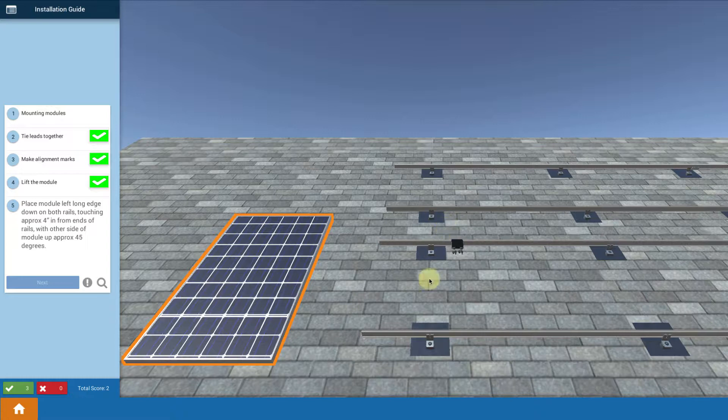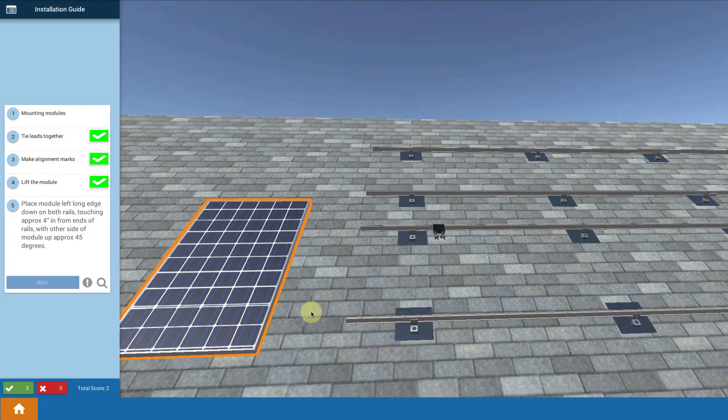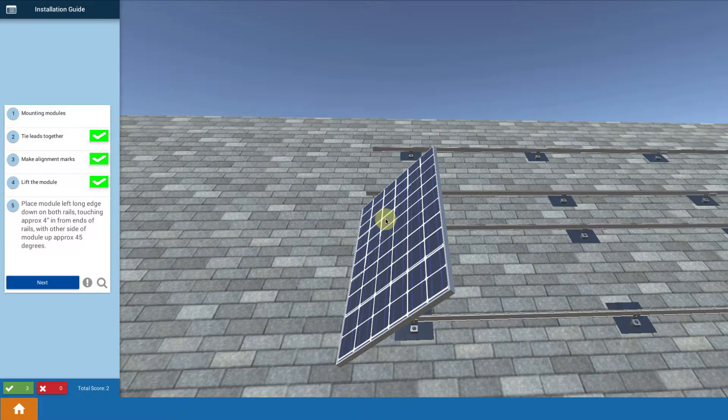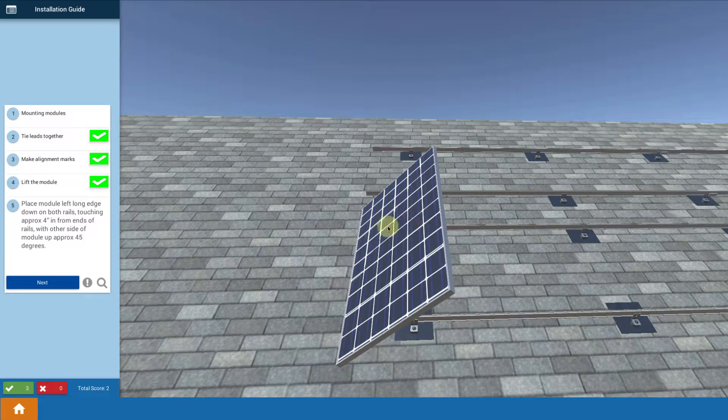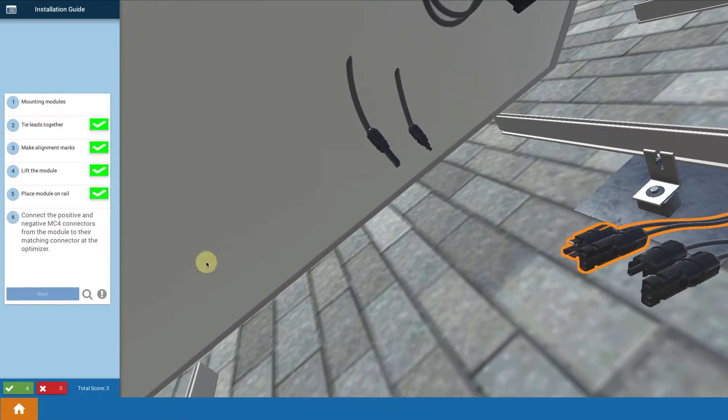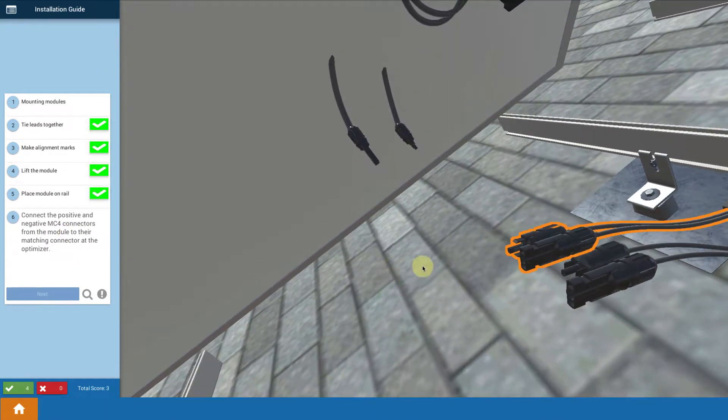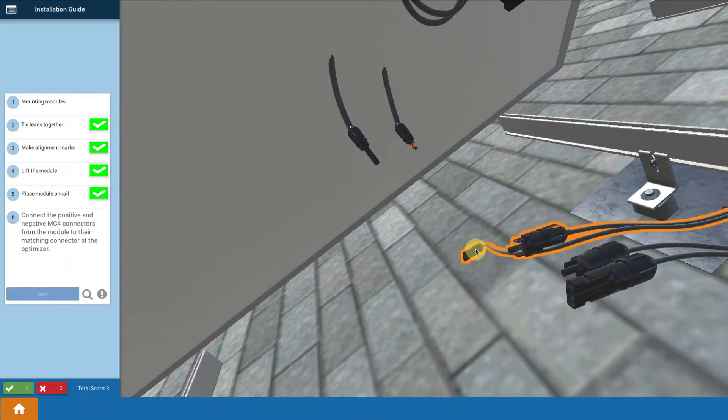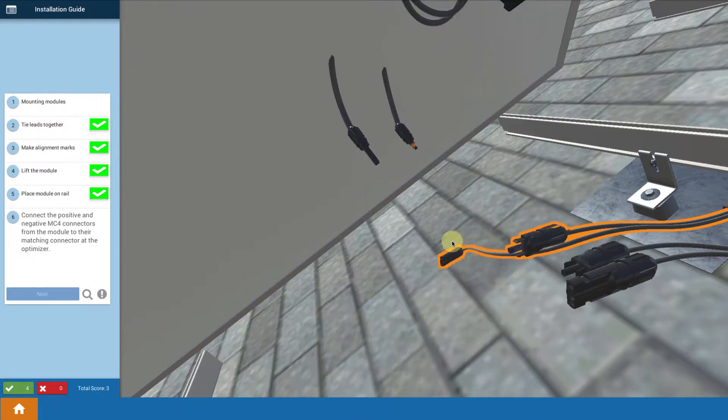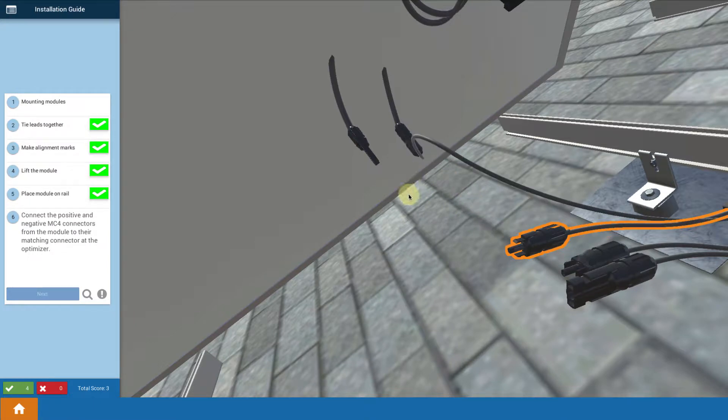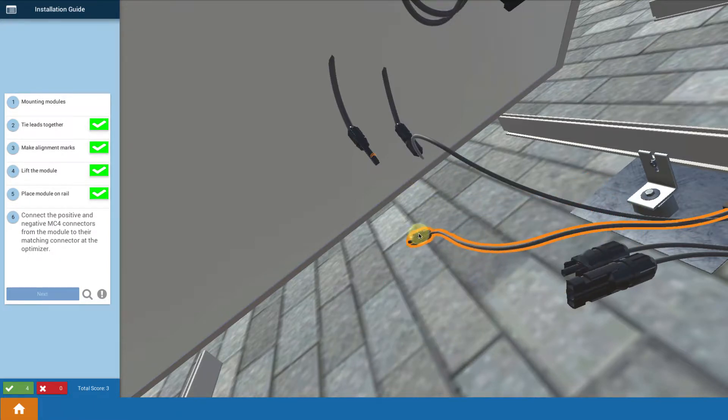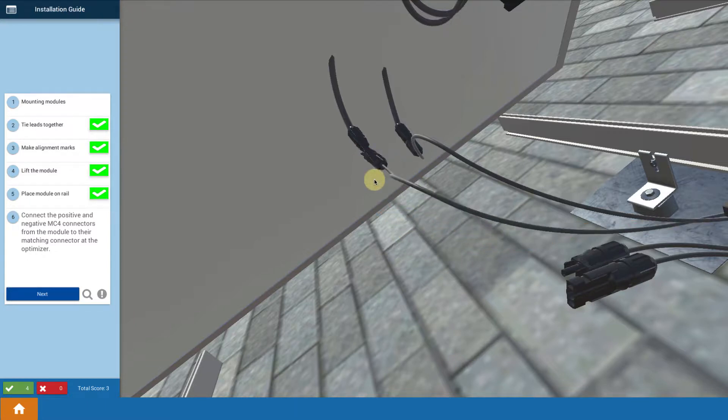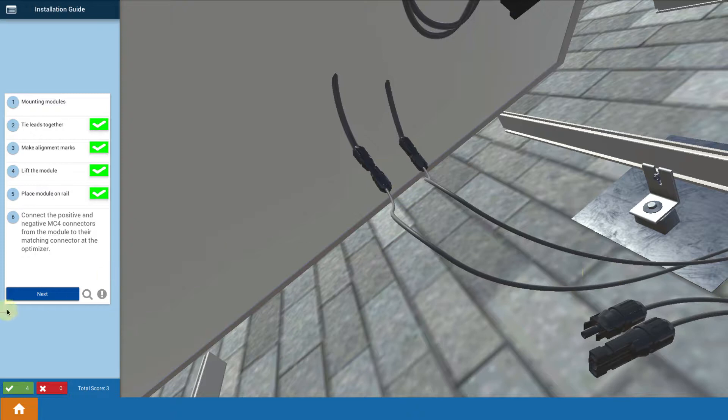So what we're going to do is start assembling it onto our rail system. So what we have you do is lift up the module and move it over, hold it at roughly a 45 degree tilt because you're going to do wiring underneath. And then underneath we've got the optimizer wires. You want to connect those to the module wires. So go ahead and grab any one of the wires. This happens to be the rectangle one and connect it to the pointy one from the module and then take the other connector from your optimizer. Bring it up and connect it to your module. So now you've connected the module to the optimizer.